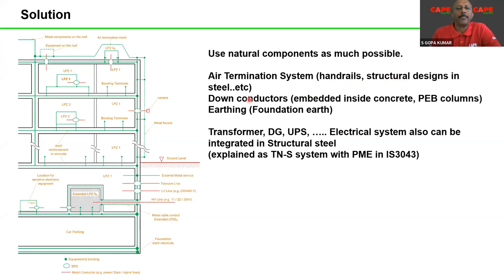This is one. Number two, down conductors. They can be embedded inside concrete. You put an additional conductor, not an MS conductor, and you don't use the rebar, because these two are major challenges, and these recommendations are made in the standard. Not galvanized steel. Better you use copper or stainless steel or copper bonded material. These three materials can be used, which do not have any side effects. Then you can also use the PEB columns. Nowadays, a lot of high-rise buildings are with PEB columns, steel columns, and those also can be used.